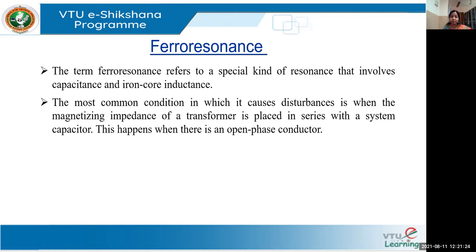We have an inductive component and a capacitive component. The inductive component is the transformer. The capacitive component refers to your power cables — these cables have a capacitive effect with respect to the ground. This kind of phenomena occurs when there is switching taking place: you are energizing or de-energizing the transformer, or when one of the lines of your three-phase system just gets open.